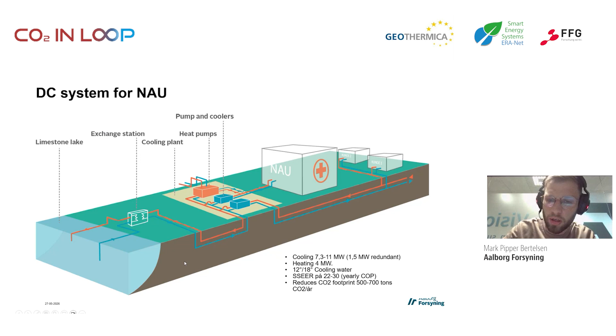However, from July until October, this lake will be too hot to meet the temperature demand of the hospital. Then we turn on the mechanical heat pumps and cool it down to the needed temperature. It has a pretty good yearly efficiency, a seasonal energy efficiency ratio of between 22 to 30. We've calculated that it reduces the CO2 footprint by 500 to 700 tons of CO2 a year.